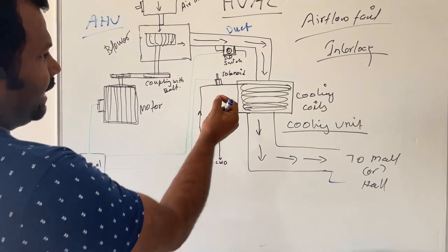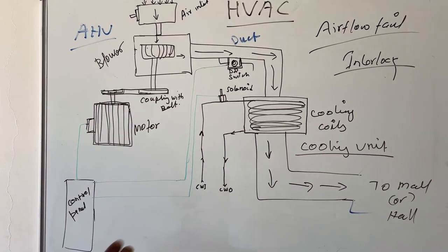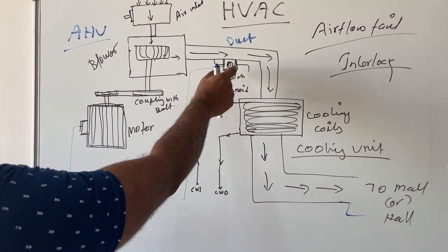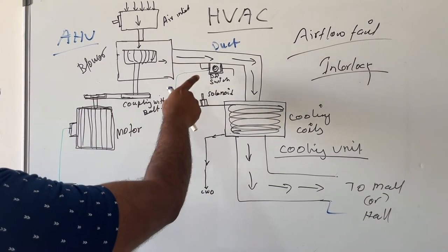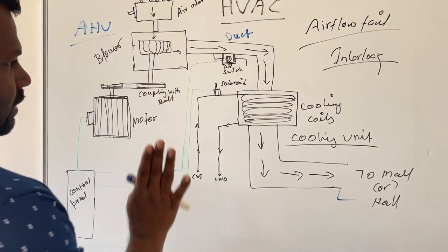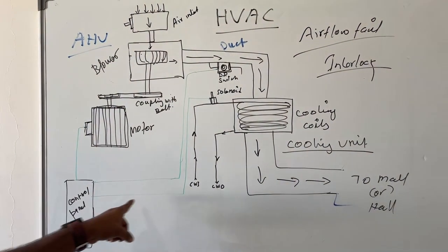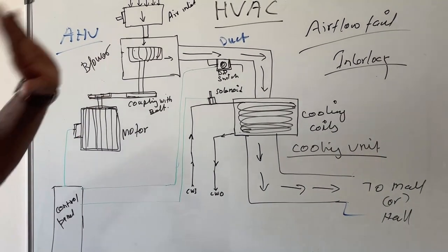What we do is install a differential pressure switch on the duct. This pressure switch is connected both electrically and through a small air inlet on the duct. A small air inlet is given to the DP switch, so that small air will pass through the micro switch which is inside the DP switch.